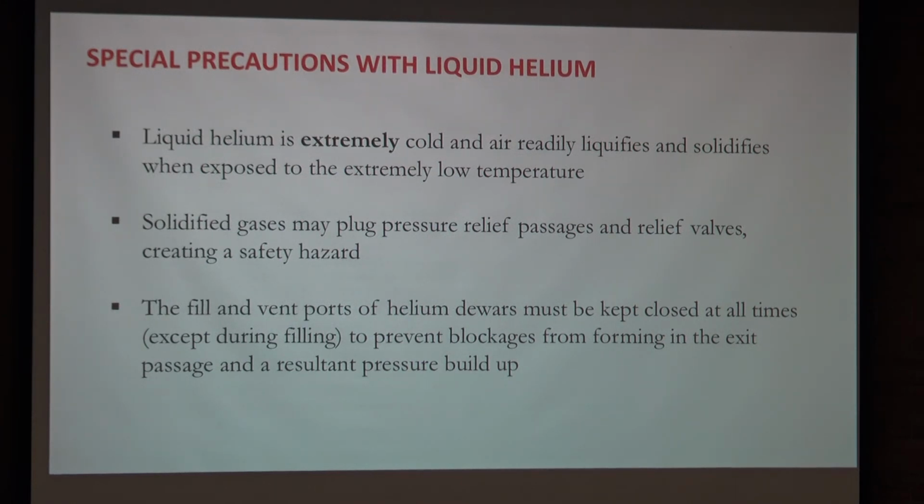Essentially anything that is in the pipes that are supposed to provide a way for your cold gas to escape, no matter whether it's water or even possibly carbon dioxide, may start to freeze and build blockages. So with such containers, be extremely careful to make sure that the pressure reliefs don't get frozen up.